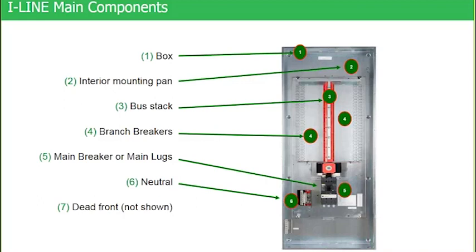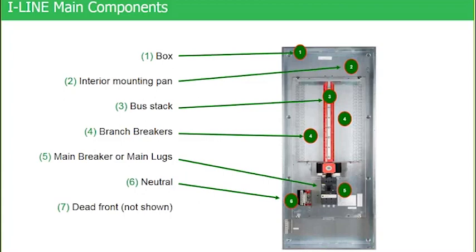We get a lot of questions through technical support that ask, can the customer go in and take that bus stack apart? And the answer is no. If they do that, it voids the warranty. That bus stack is a very intricate assembly. It has many pieces and parts to it, many little spacers and connectors within the bus stack so we have all the proper spacing.